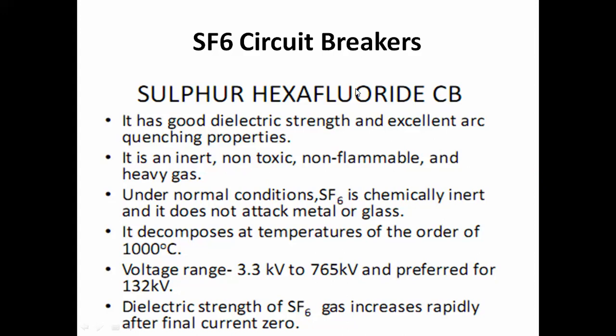This type of circuit breaker can be used in a wide range of voltages, starting from 3.3 kV to 765 kV, and is preferred for 132 kV. So in a power system, we generate the power at 11 kV and we have to step up the power to 132 kV, 66 kV, 220 kV, 440 kV, depending upon the distance between the generating end and the distribution end.